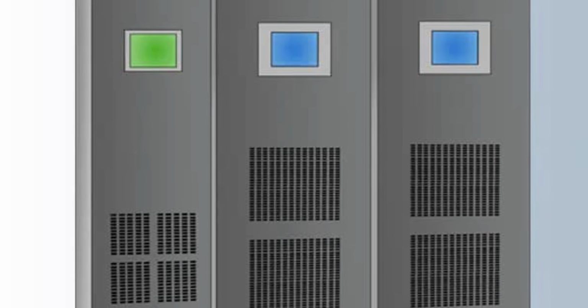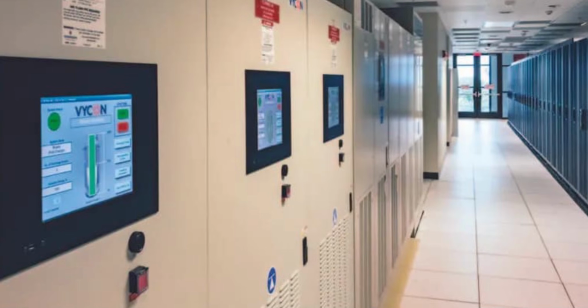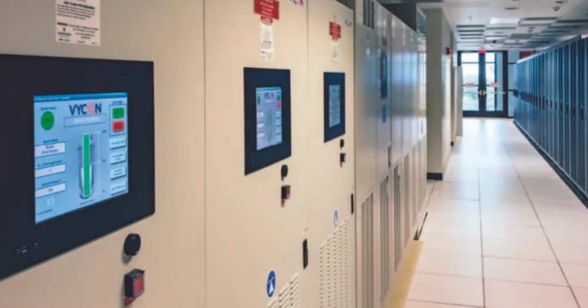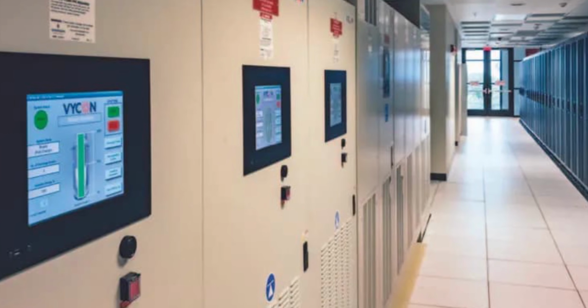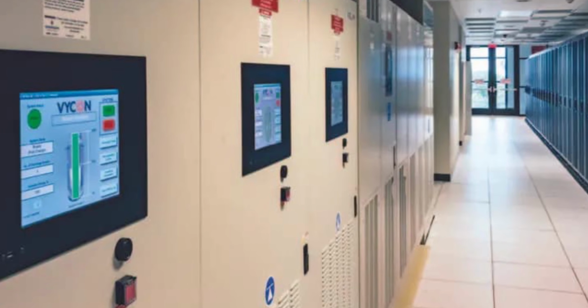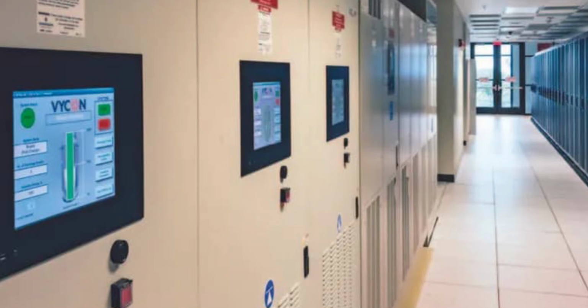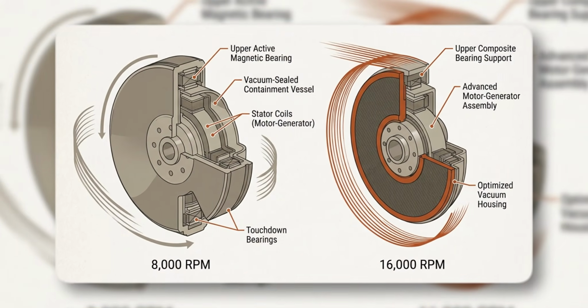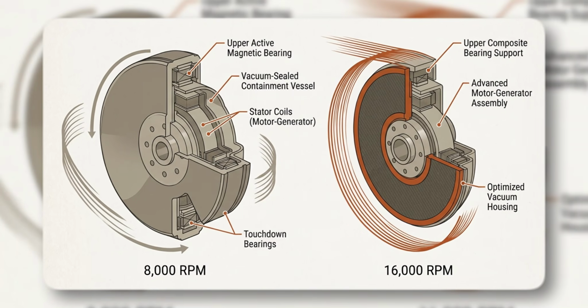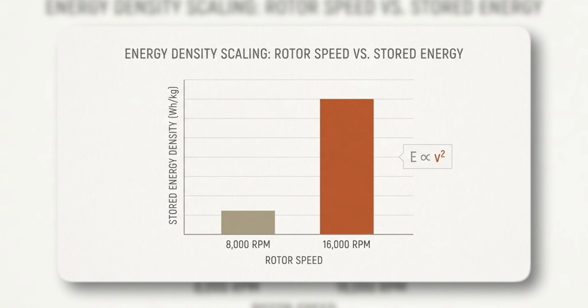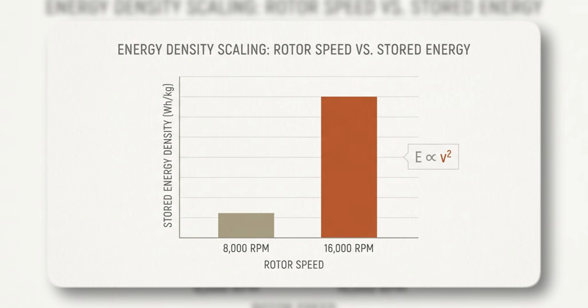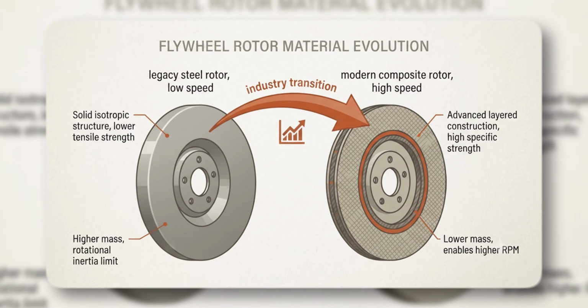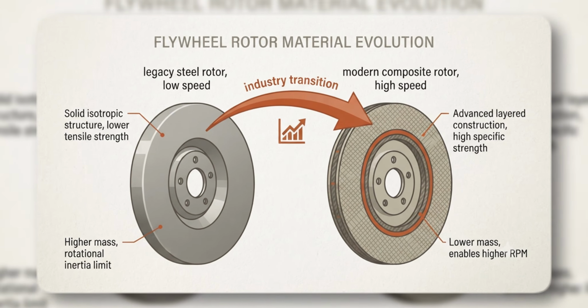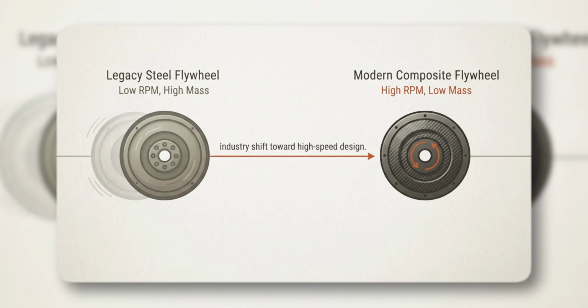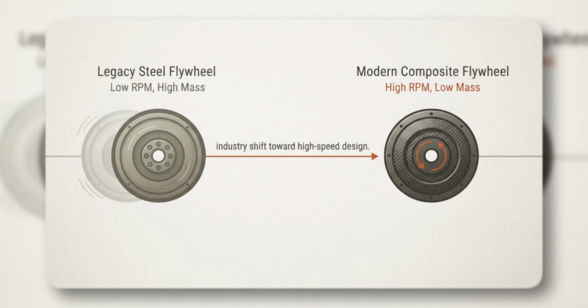Read that again, because it matters. Double the RPM of a spinning rotor and you do not double the stored energy. You quadruple it. This is why the difference between a flywheel spinning at 8,000 revolutions per minute and one spinning at 16,000 revolutions per minute is not a modest upgrade. It is an entirely different category of energy density, and it is the reason older, slower steel flywheels have been quietly getting phased out across the industry in favor of high-speed designs.